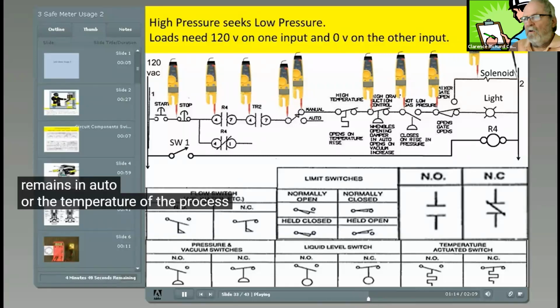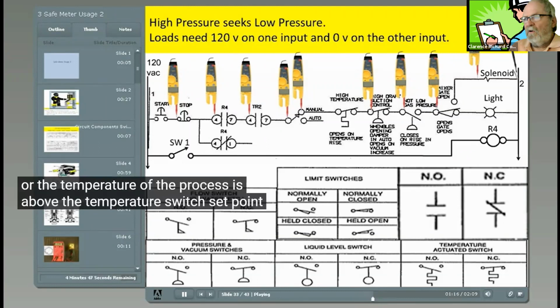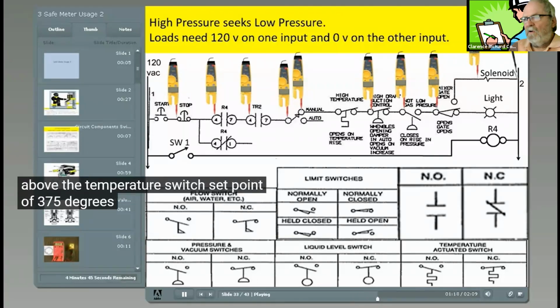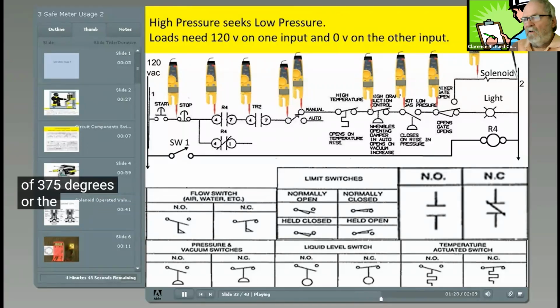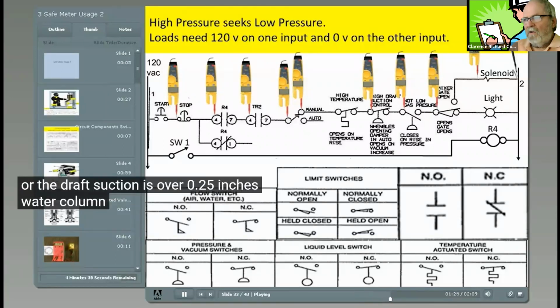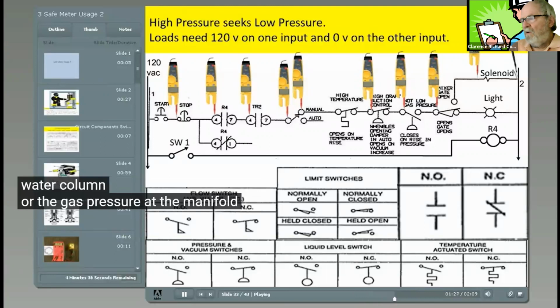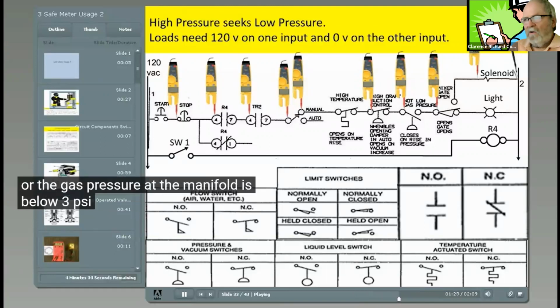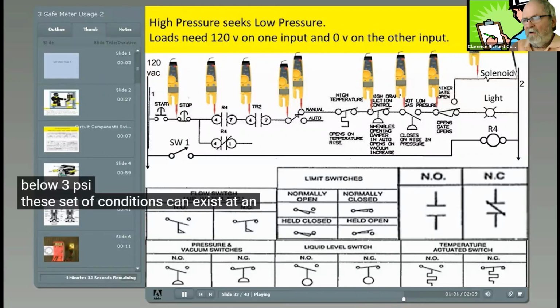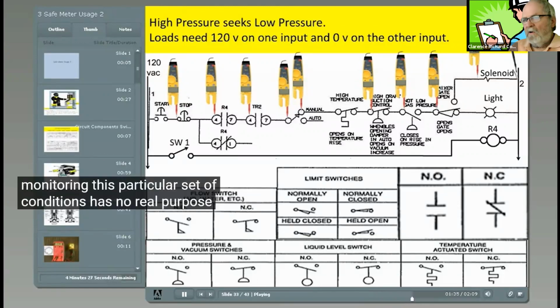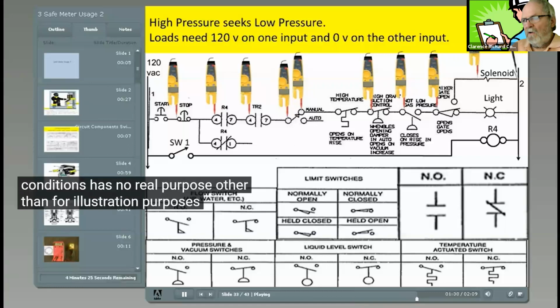or the temperature of the process is above the temperature switch set point of 375 degrees, or the draft suction is over 0.25 inches water column, or the gas pressure at the manifold is below 3 psi. These sets of conditions can exist at an asphalt plant. Monitoring this particular set of conditions has no real purpose other than for illustration purposes.